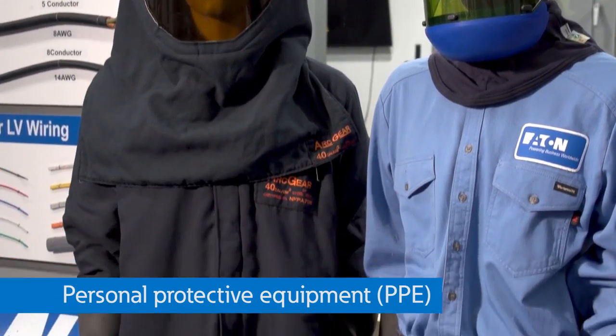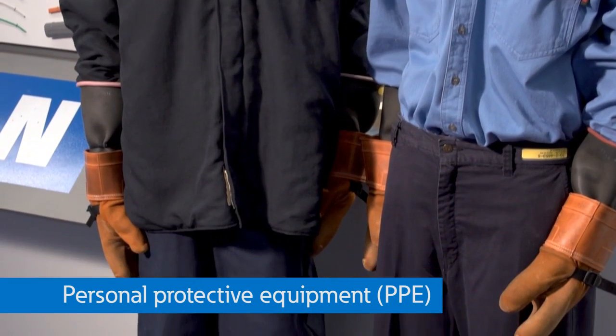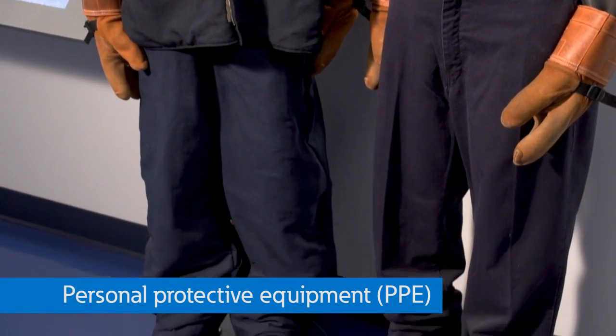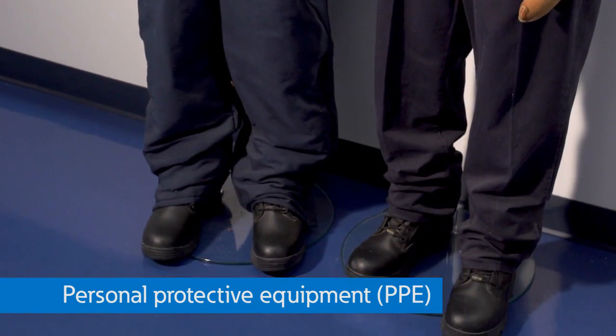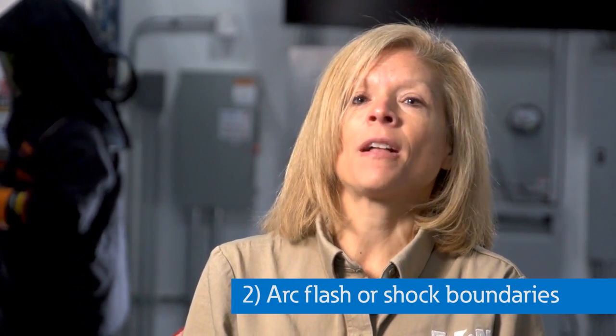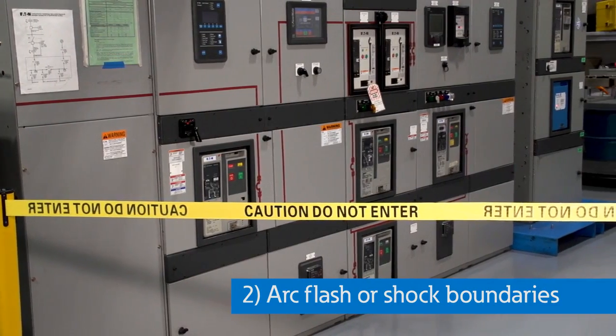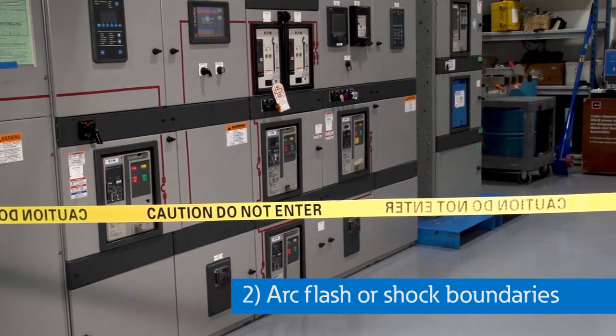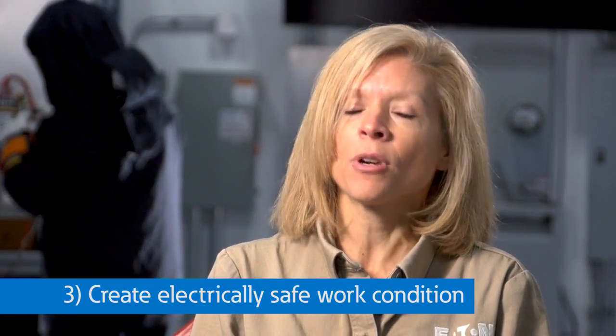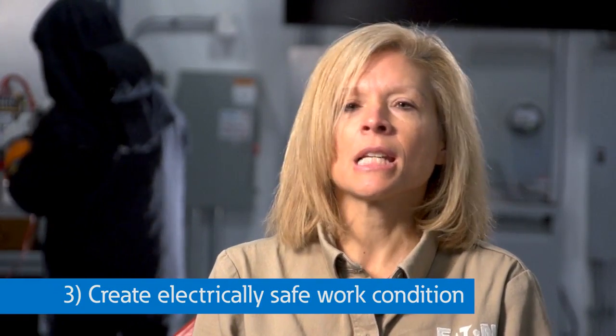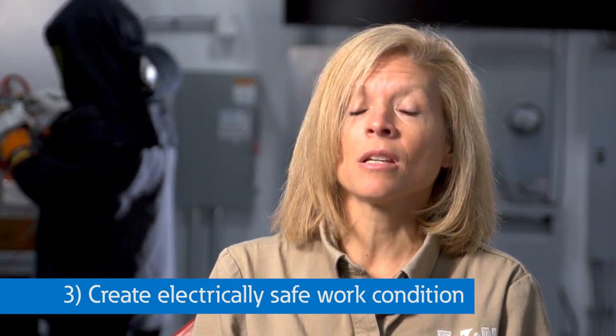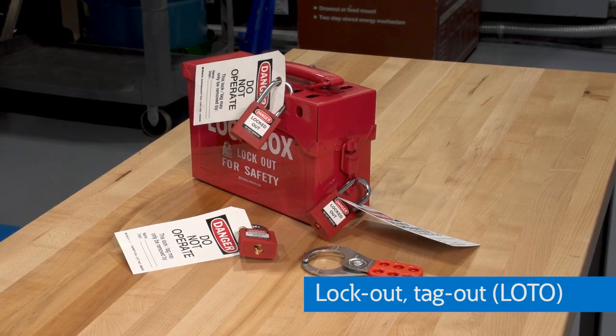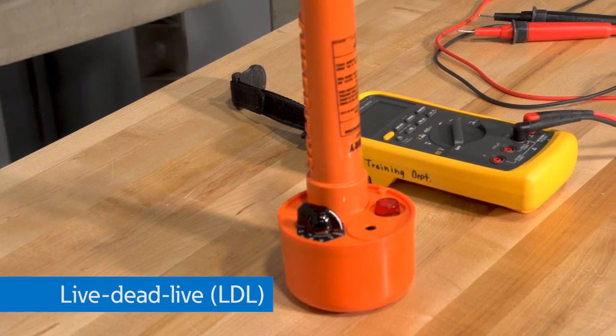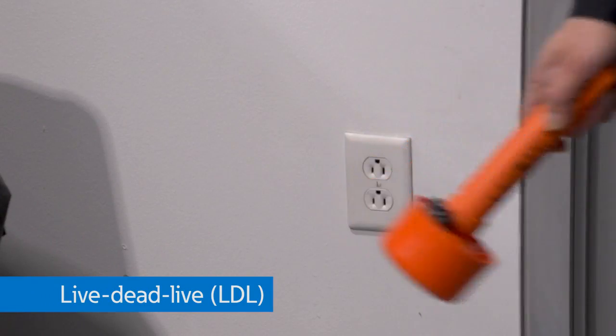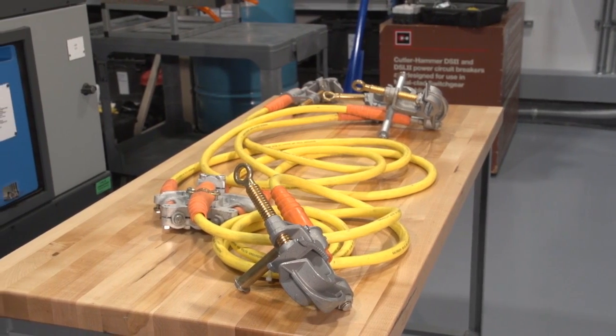Personal protective equipment must be identified specifically for the job site, considering potential arc flash levels and shock hazards. Boundaries are evaluated for arc flash and shock hazards, and the more restrictive boundary is set for the job site before doing work. Next, you must create an electrically safe work condition. This includes disconnecting and/or isolating sources, lockout, tagout, or LOTO, checking for the absence of voltage using live dead live or LDL procedure, and applying grounds as necessary.